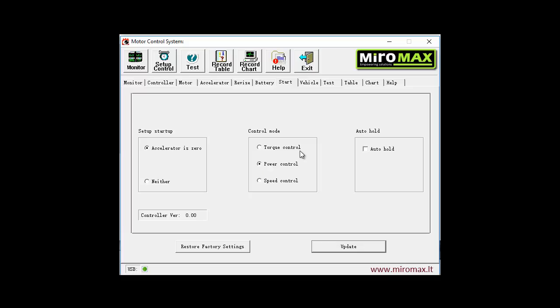This is speed control, one of the basic settings, and the user should set this accordingly. To the left side we can see a setting which is intended to control how the motor starts. By default, the accelerator should be at zero position for the motor to start. In other words, if it is set at some different position, not zero, then the motor will not start until the accelerator is released to zero. If it is activated again, the motor can start.